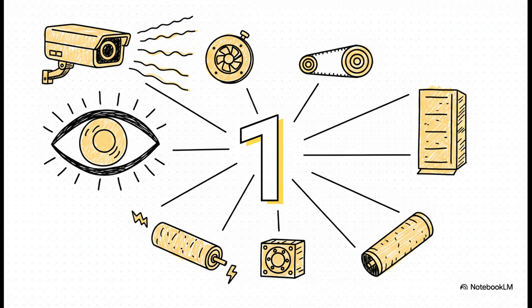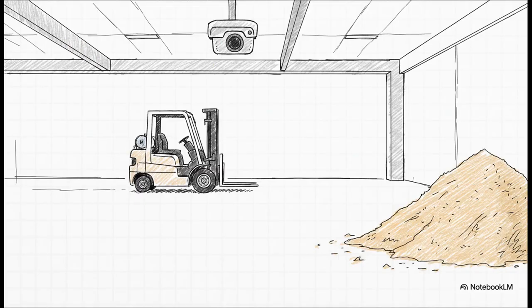1. A single continuous AVIAN thermal camera monitors an entire production zone. Every single motor, bearing, belt, roller, duct, and electrical connection within its field of view, covered by just one device. You're effectively replacing dozens of fragile physical contact points with a single overarching eye that monitors the actual temperature of your entire operation. So what does this actually mean for cost efficiency and durability?